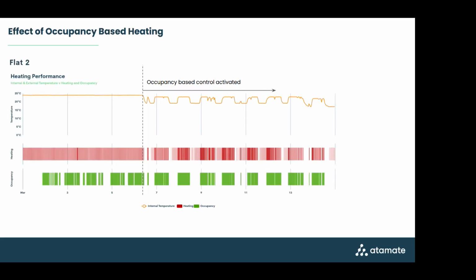Just looking at real basic stuff, what we've got here is a time series of data. These big green blocks at the bottom are showing occupancy. The occupancy is a combination of PIR detectors, passive infrared detectors, like a security alarm type thing, or radar - we use both. Typically we're also using carbon dioxide sensors, and we're looking at the decay of CO2 for knowing when a room's unoccupied.